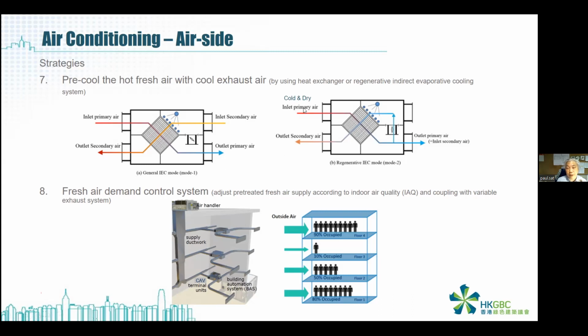Okay, and also if the primary air becomes cool and dry, like in winter, they can use the regenerative mode to directly use this cooling to cool the primary air. This is the regeneration mode and this is the general mode. This kind of technology is most likely used in areas that do not require very precise space temperature or a very large amount of cooling, such as in wet markets. So in Hong Kong, the housing authority markets may be using this kind of technology.